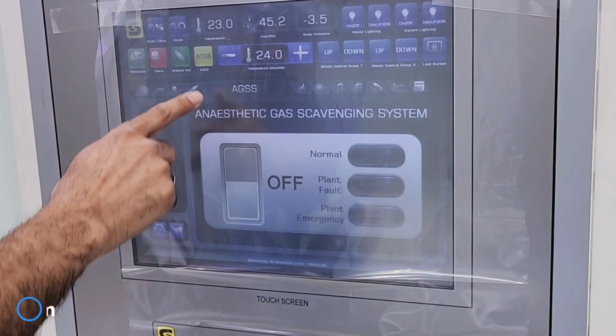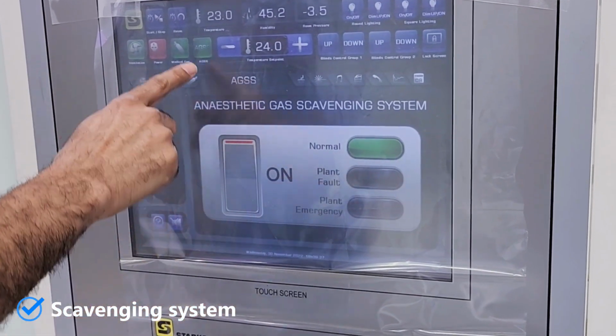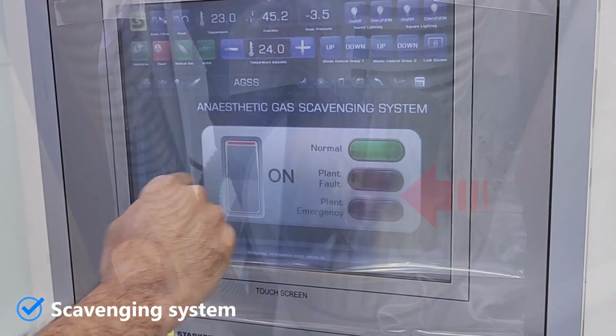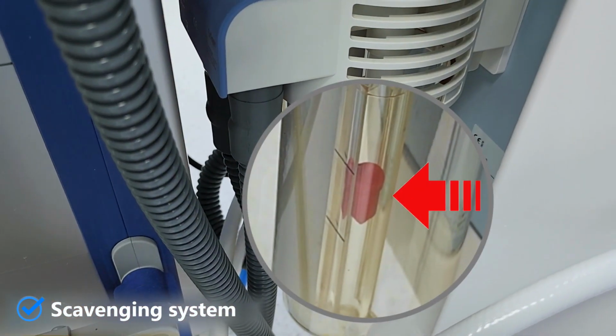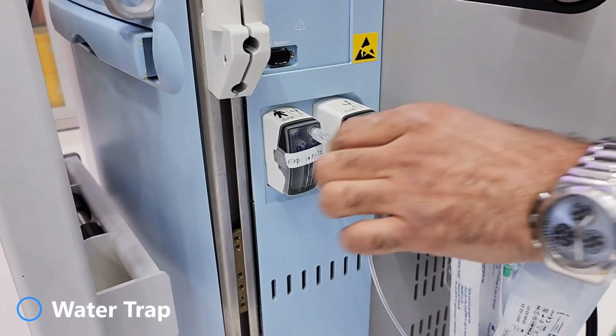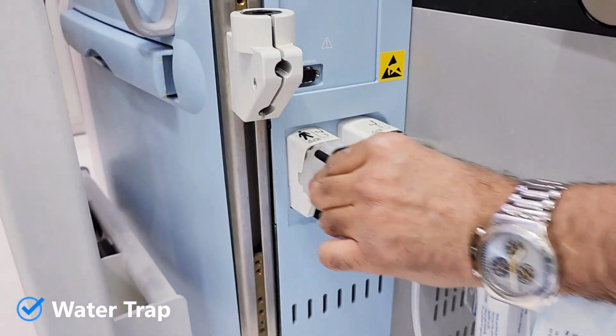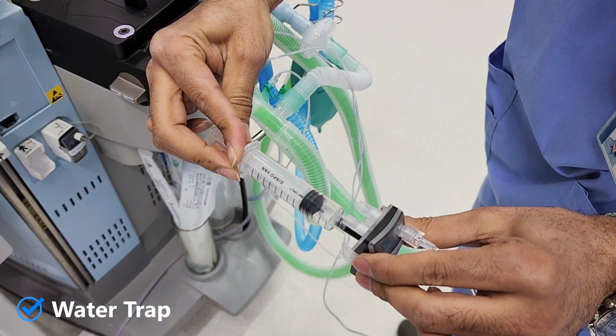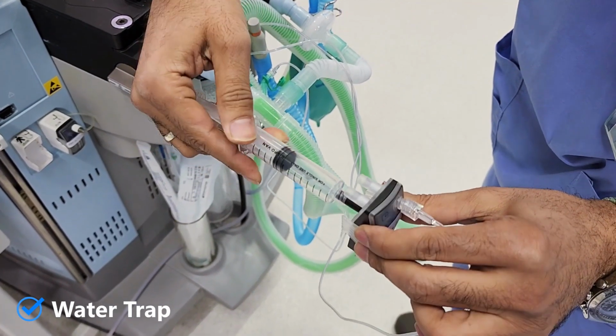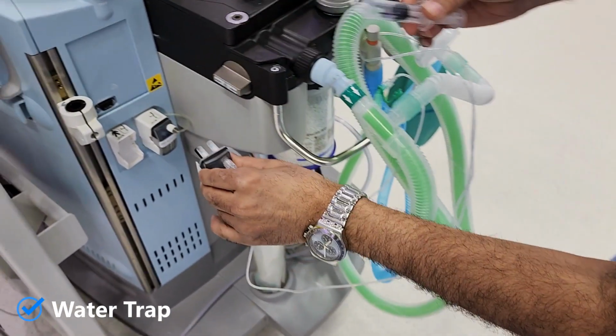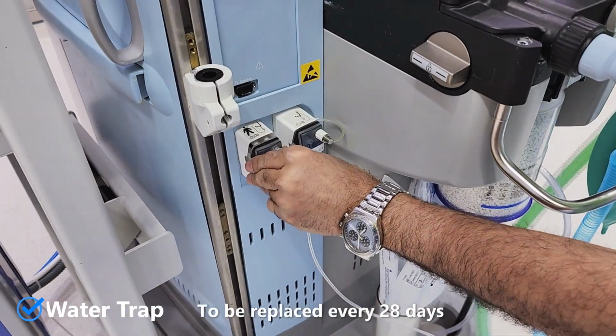The scavenging system has to be switched on from the main panel on the wall, and confirm that the bobbin behind the anesthesia machine is floating between these two black lines. To remove water from the water trap, attach a syringe to the dark port and aspirate. And make sure it is well inserted back. It should be replaced every 28 days.